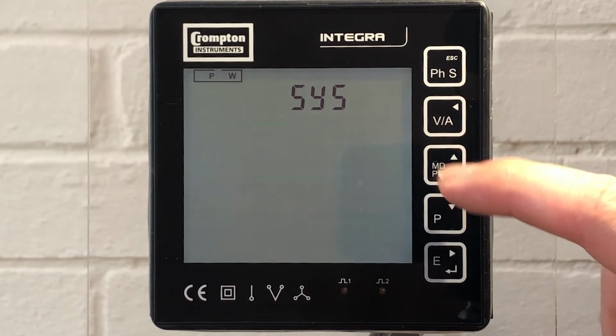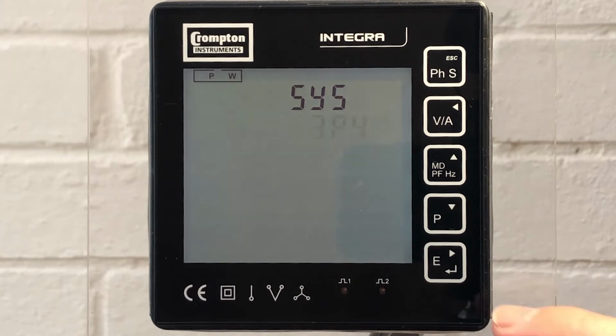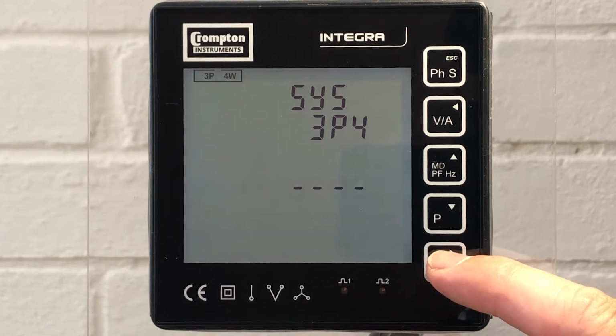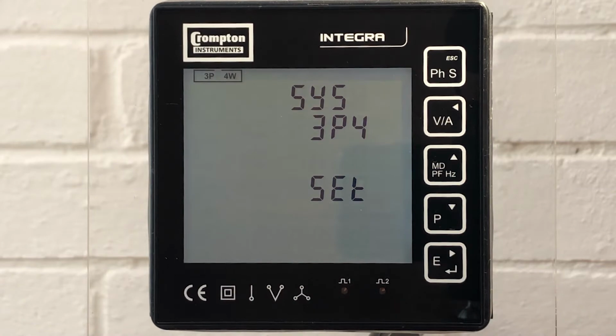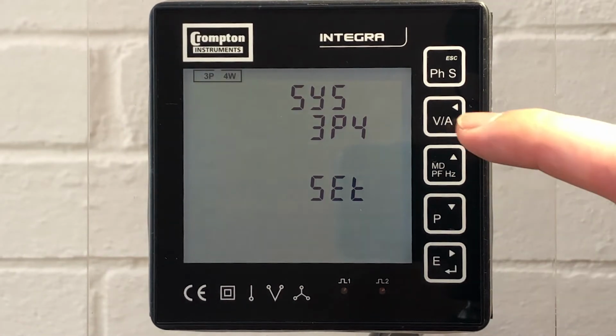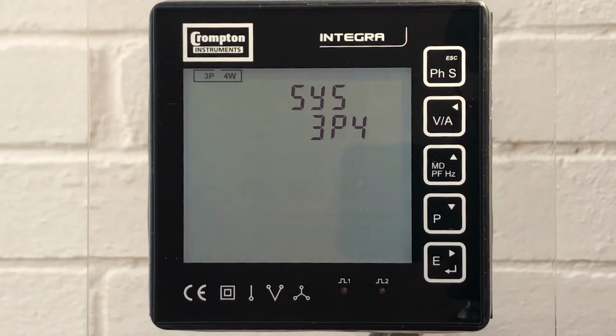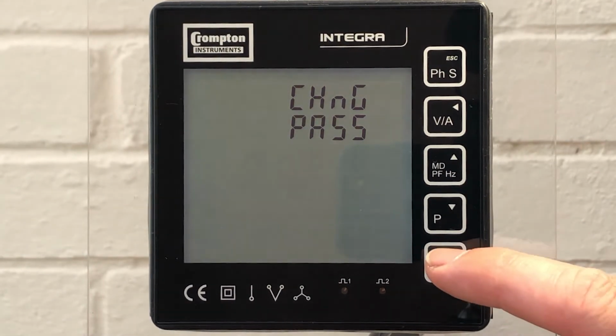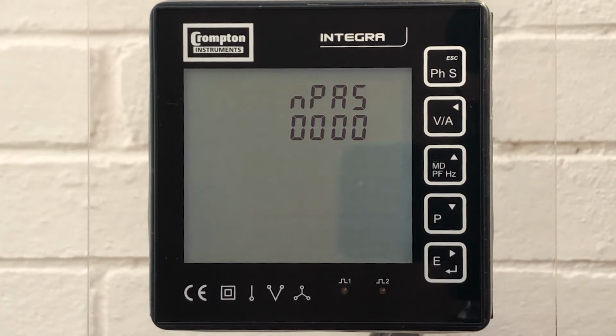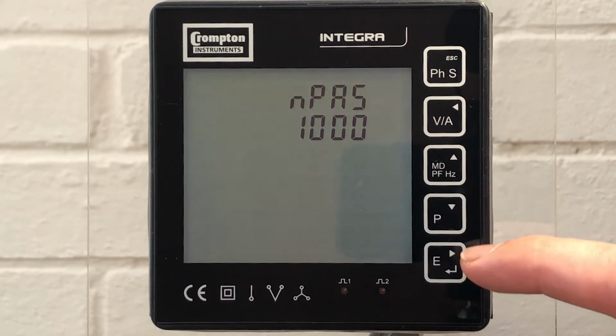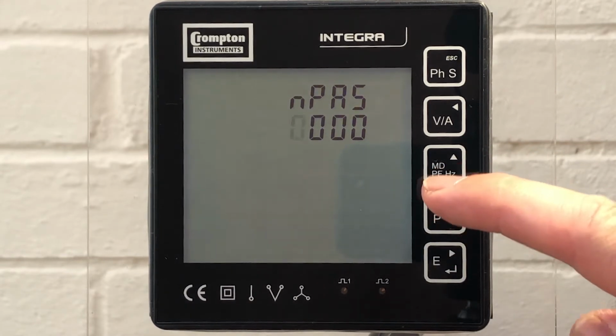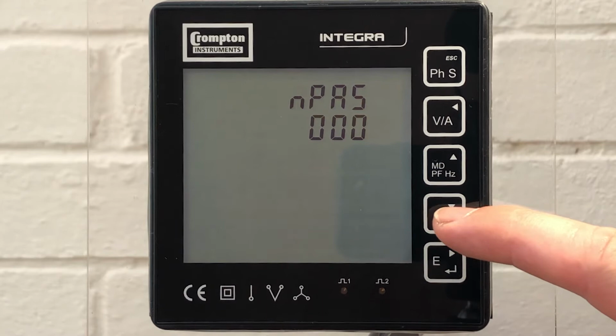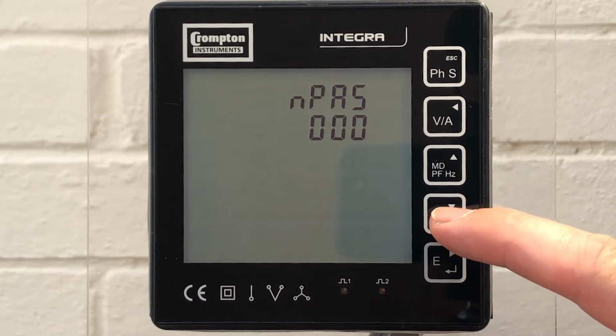To select the system type, hold down the E button for 2 seconds until you see the word set. The system is now set as 3-phase 4-wire. Press the VA button to escape out of the system type and arrow up to the change password screen. Pressing E will make the characters flash and you are able to change the password to any 4-digit number between 4 zeros and 9999.